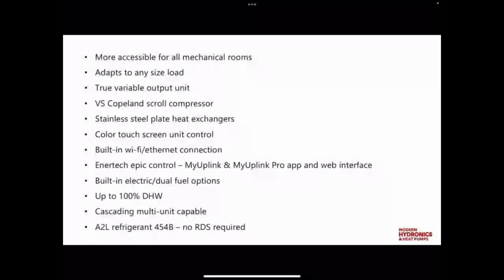And we are offering two different versions of this unit. We have a built-in 9 kW electric backup heater, or there's a dual fuel option, which we'll be talking quite a bit about. To my knowledge, this is the first hydronic geothermal unit that offers true dual fuel compatibility, and I'm pretty excited to show that off. It's really cool. You can do up to 100% of domestic hot water with this unit. We do have the ability to cascade multiple of these units together, and we'll get into how that works. And this unit does feature A2L refrigerant. We are using 454B, and it is below the mitigation level, so there is no refrigerant detection system required.